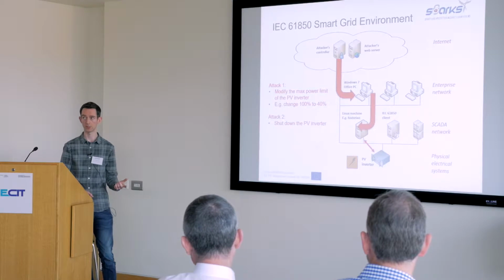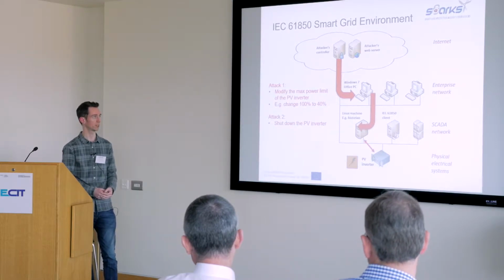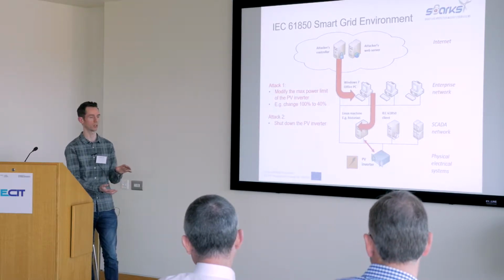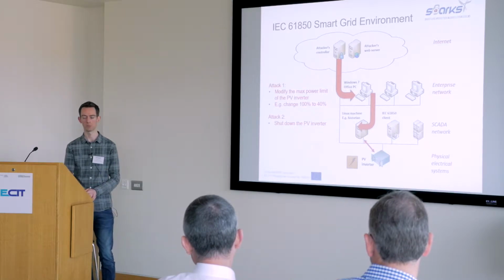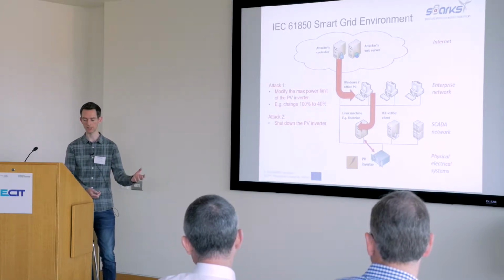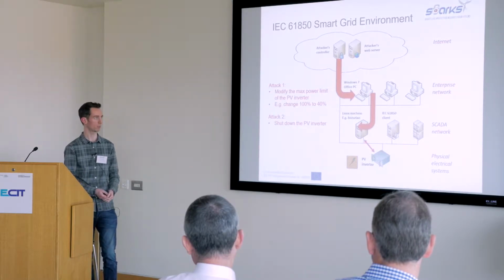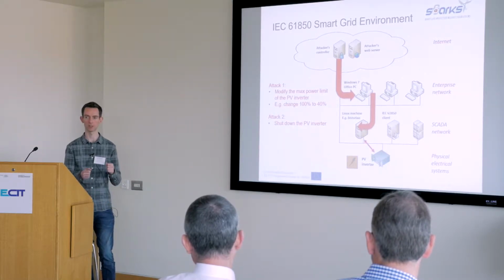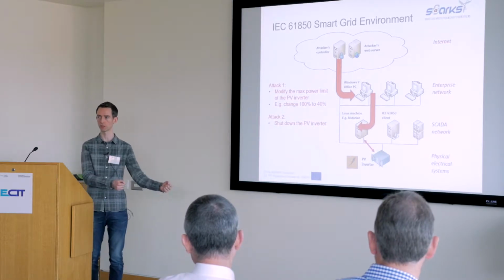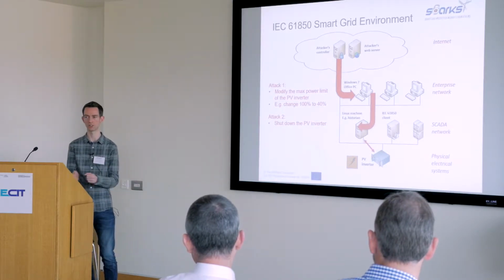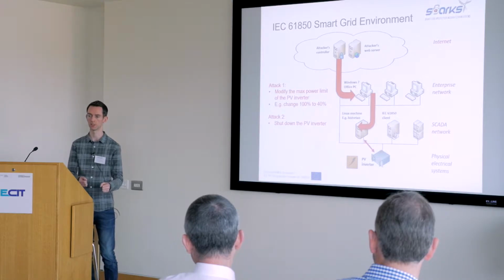With this particular PV system, we're able to modify a specific field called the maximum power limit. The effect is to change the output of the inverter. For example, if the operator wants it at 100% output, we can say don't do that, change it to 40, and it changes to 40. But what the operator sees on their screen is everything's at 100, everything looks good—but out in the field it isn't.